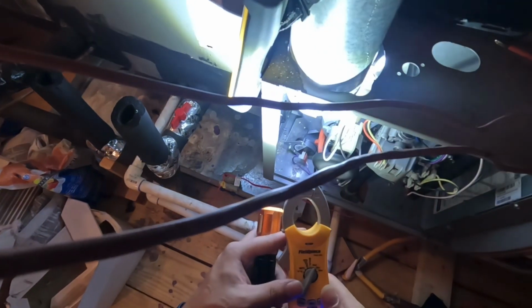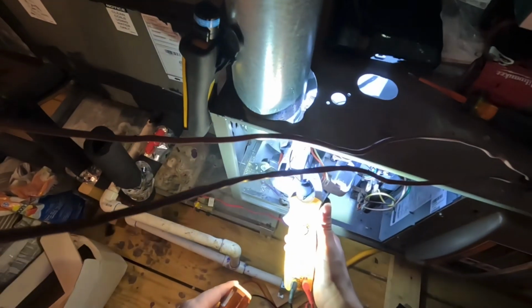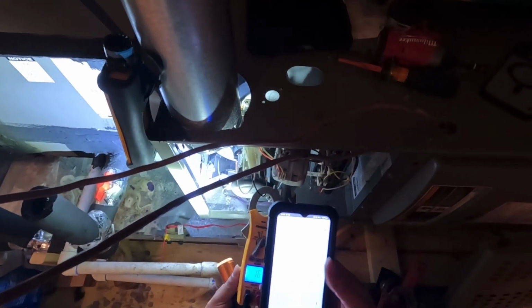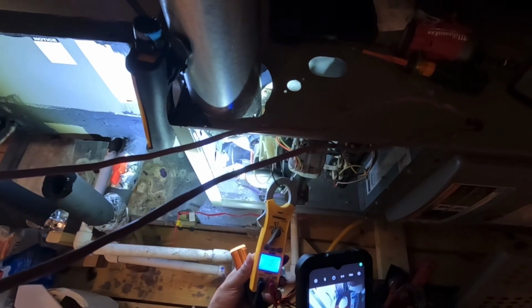Okay, so the amps - load run amps, fluctuating amps, so it should be 1.2 on here, the amps, 1.2. Load run amps 1.5, so that's pretty good. I'll take a picture of this. It's a little overamping, but it's not too bad.